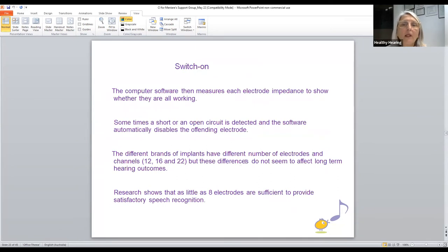And then the computer will measure first the impedance of each electrode. So as you know from Professor Gibson's talk, the electrode array of the cochlear implant has several electrodes, and each electrode will respond to a certain pitch, certain sounds, some low pitch going all the way to high pitch sounds. So the computer software will measure first the impedance of each one of those electrodes. For example, Med-El has 12 electrodes, AB has 16 electrodes, cochlear has 22 electrodes. So the software measures all of that and identifies if they are all working.